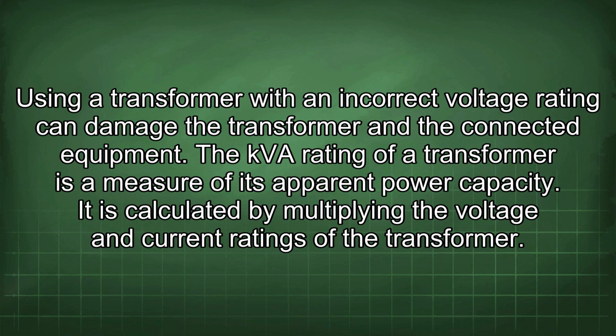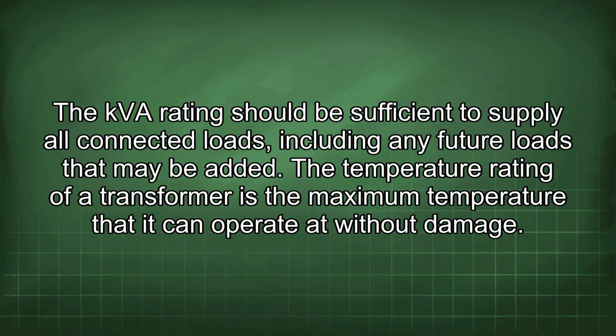The kVA rating of a transformer is a measure of its apparent power capacity. It is calculated by multiplying the voltage and current ratings of the transformer. The kVA rating should be sufficient to supply all connected loads, including any future loads that may be added.